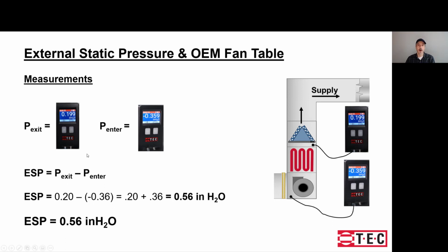So let's talk a little bit about what we saw. Steve made two measurements on the furnace. At the exit, he measured just under 0.2 inches, and at the entrance, he measured just about negative 0.36. Remember, we're always going to take the total difference there to get the pressure change across that OEM equipment. So in this case, when we subtract those two or add the two values together, we get about 0.56 inches of H2O, or inches water column.